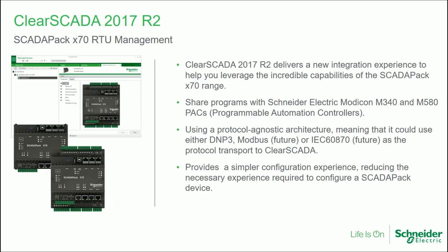Also, we have in ClearSCADA 2017 R2 the management of the SCADAPack X70 devices. These devices presently will be using DNP3 and also Modbus, and what we've done is extend the DNP3 driver to enable the configuration download of all of the features that these particular devices support. So for example, we can download logic sequences that are being created with Schneider's Unity programming engine, and also we can download the configuration of points and persistencies and all sorts of outstation features.